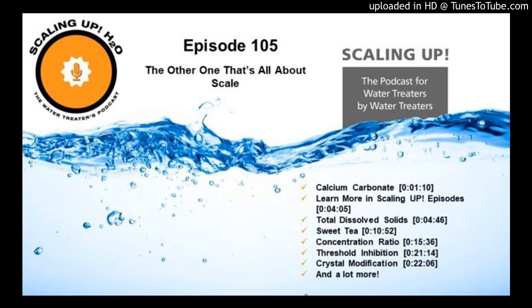So what we do is we do water tests. We figure out what's in the incoming water and how it's concentrating up in the system that we are treating. We then figure out which ion is going to scale first, and then we're going to set a conductivity bleed so we never get up to that situation.